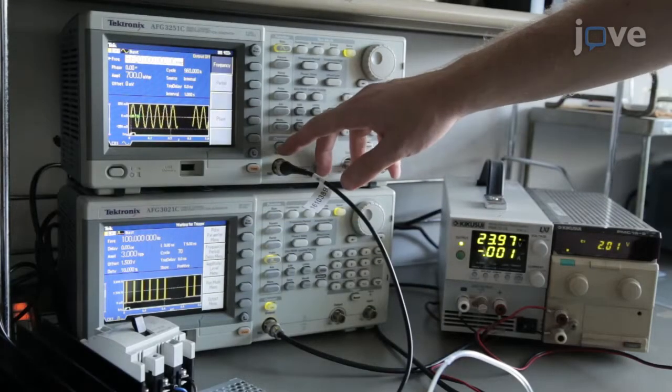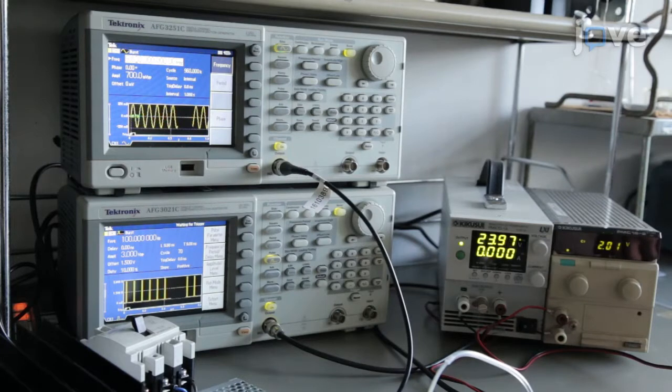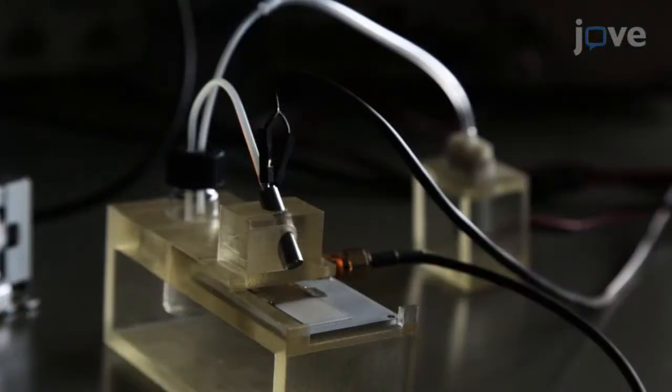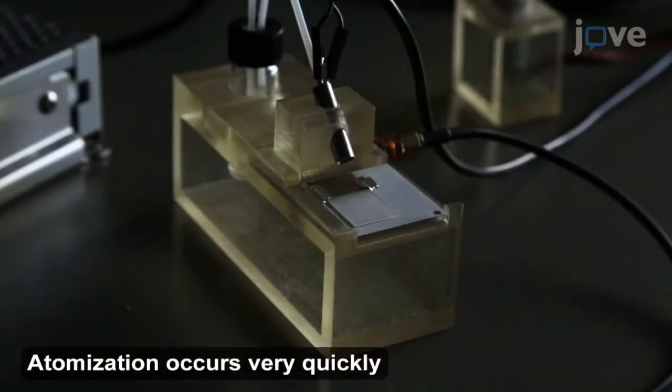Apply the RF burst signal to the device for as long as needed to atomize the droplet. Observe the surface of the device to witness atomization and to inspect the remaining liquid droplet.